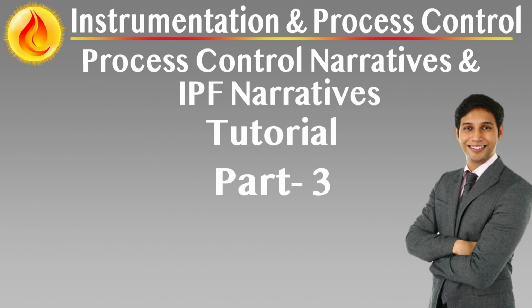Alarm narratives, purpose and role in alarm management. Alarm narratives provide structured descriptions of process alarms that are not part of formal trip logic, but are critical for operator awareness and timely intervention. Unlike IPFs, which bring the system to a safe state automatically, alarms rely on operator response to prevent escalation of abnormal conditions. Well-documented alarm narratives support effective alarm classification, rationalization, and implementation, ensuring that every alarm serves a clear operational purpose and contributes meaningfully to process safety and efficiency.